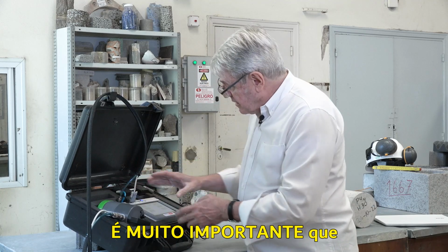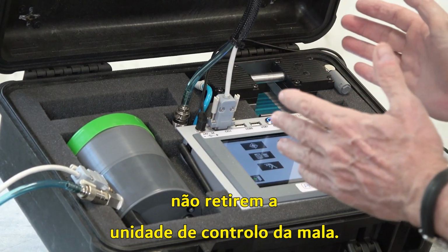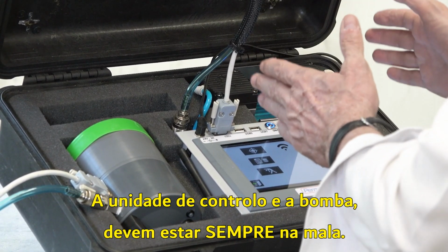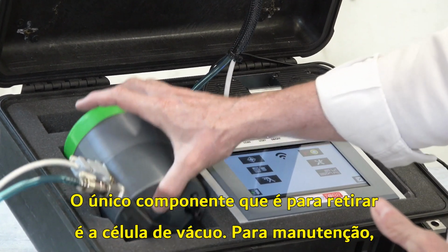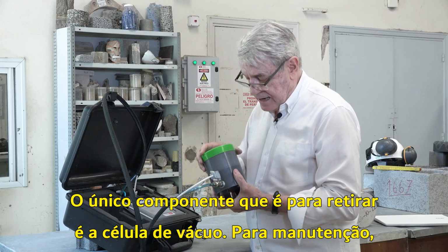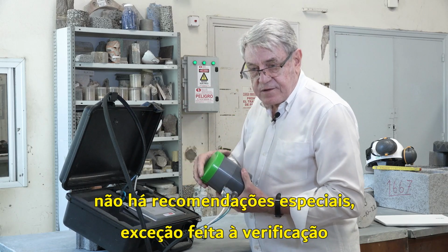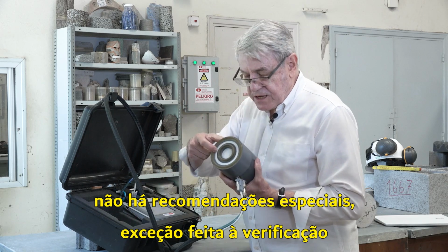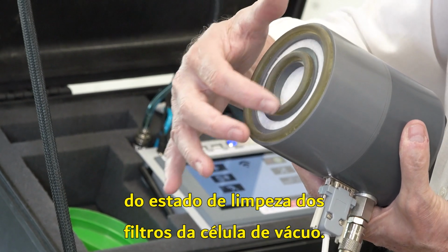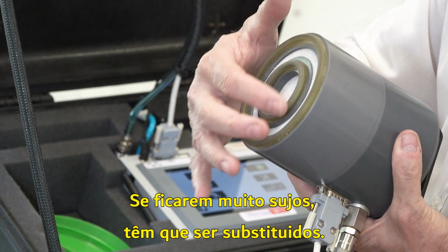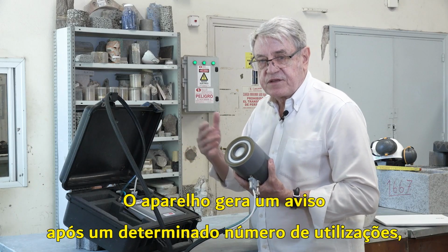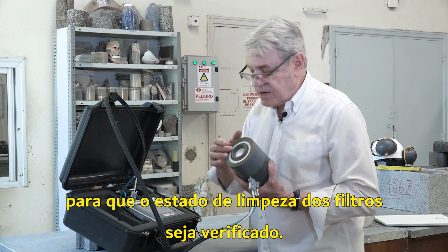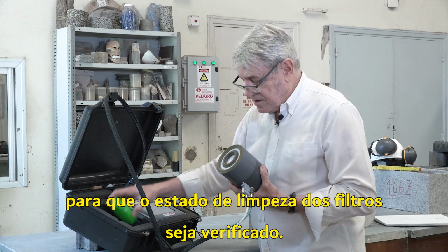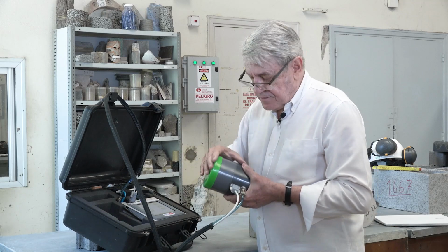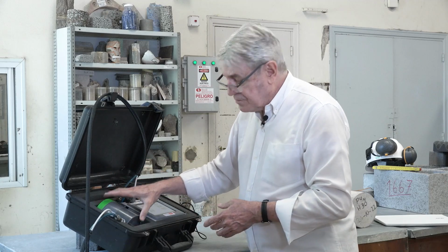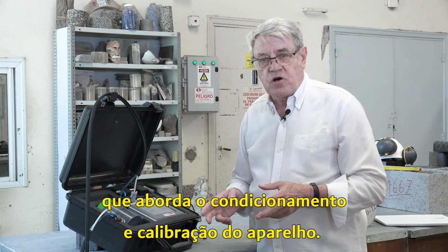Very important is that you should not remove the unit from the case. The unit and the pump have to stay always in the case. The only thing that you can remove is the vacuum cell. And for maintenance, there are no particular recommendations except to check that the filters of the vacuum cell are clean. If they become very dirty, they have to be replaced. There will be a warning in the instrument after a certain amount of uses that you have to check the cleanness of the filters. With this we finish the installation part, and now we will move to the next video, which refers to the conditioning and calibration of the apparatus.